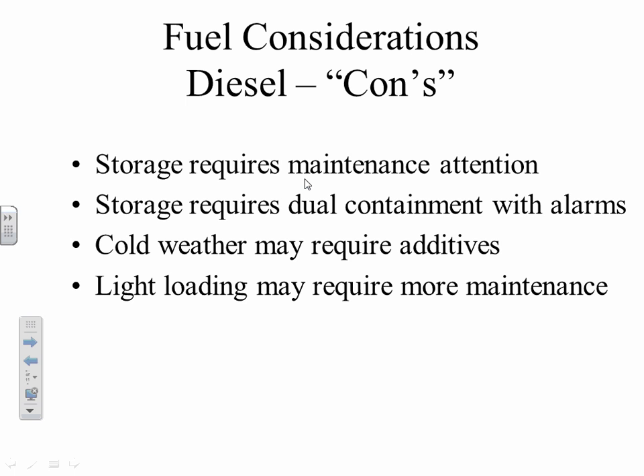Also on the con side is storage requires dual containment with alarms. You folks may or may not be able to remember maybe 10 years ago, you'd drive by gas stations, you'd see backhoes doing stuff with the tanks, taking the tanks out and so on. Well, that's kind of what started this. What was happening was we had electrolysis acting on the skin of a single wall tank, a tank that was buried. When I mentioned the phone companies in Oregon, they got a lot of mountains, and I put a lot of fuel tanks up in the mountains that were advertising 20-year guarantees and so on. But they were all single wall. And over time, electrolysis would act on the skin of those iron tanks, and it would actually corrode those tanks. It took a long time, but it actually had a small amount of current that was corrosive. And that was true of the gas stations, too.